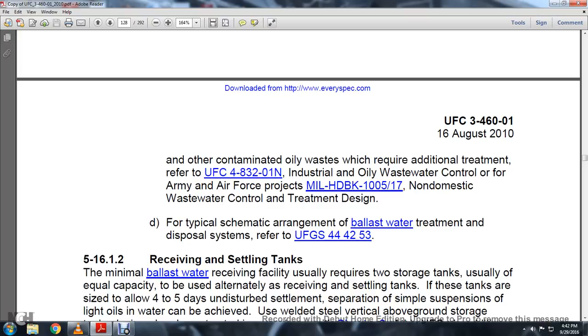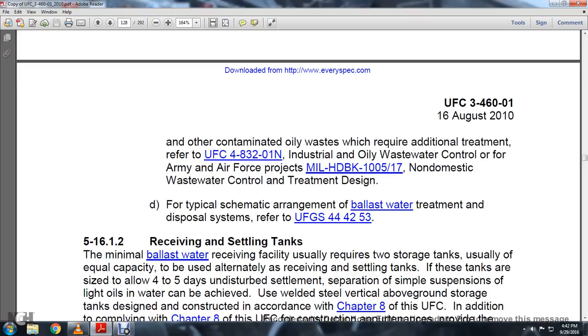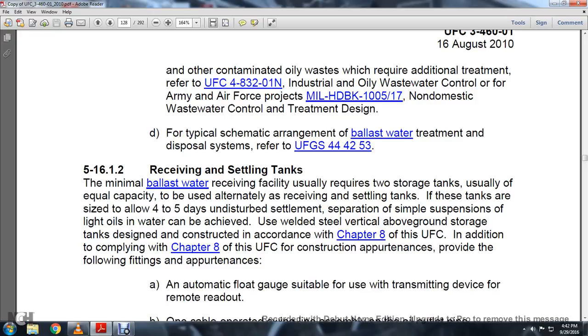Non-domestic wastewater control and treatment designed for typical schematic arrangement with the ballast water treatment and disposal. Refer to the UFGS 44 42 53. 5-16.1.2 Receiving and settling tanks. Minimum ballast water received at the facility usually requires two storage tanks, usually with equal capacity, to be used alternatively as receiving and settling tanks. If these tanks are sized to allow 4 to 5 days of undisturbed settlement, separation with simple suspension of light oils into the water can be achieved.